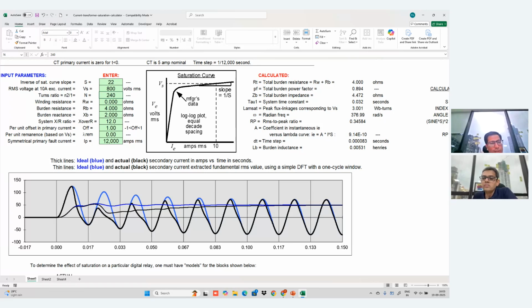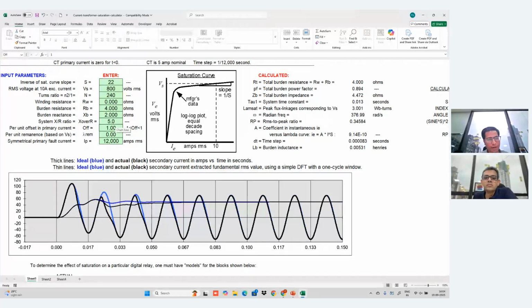So what we can do here is also, if I change the X by R of the circuit, yes, X by R will also affect the calculation. Now you can see the error, which was very high, is reduced. So if the burden and everything is calculated before the design of the CTs, at the design level, then you can have the proper CT selection done before it is installed.